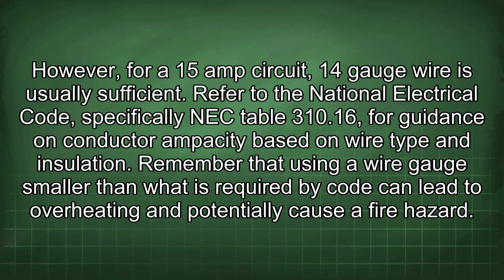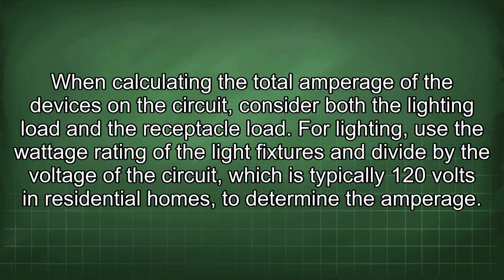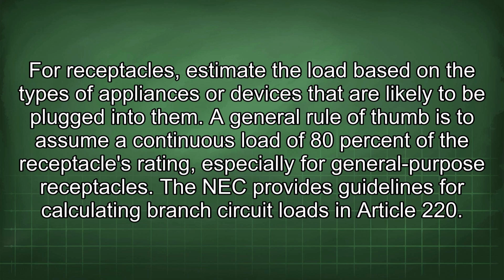When calculating the total amperage of the devices on the circuit, consider both the lighting load and the receptacle load. For lighting, use the wattage rating of the light fixtures and divide by the voltage of the circuit, which is typically 120 volts in residential homes, to determine the amperage. For receptacles, estimate the load based on the types of appliances or devices that are likely to be plugged into them. A general rule of thumb is to assume a continuous load of 80% of the receptacle's rating, especially for general-purpose receptacles. The NEC provides guidelines for calculating branch circuit loads in Article 220.